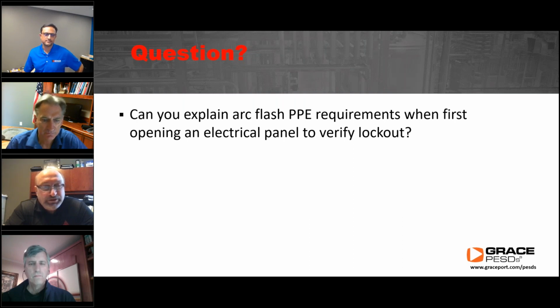So this is the interpretation part of 70E and Z462, where you've really got to look at what it says, but I think you have to do your own risk assessment. For instance, do I need arc flash PPE to open up a junction box, right? It would imply that any hinge door requires arc flash PPE. Or a PLC or a DCS control panel, do I need arc flash PPE to open up those hinge doors? So I would beg the user to make sure that, on this particular work task, you look at the electrical equipment that the hinge door is on, what's behind the door, and the condition of maintenance, and then decide if the arcing fault is likely to occur or not. Okay. Thanks, Terry.